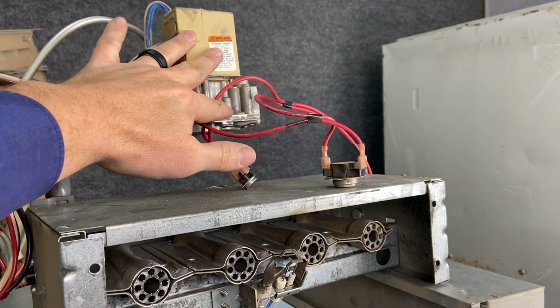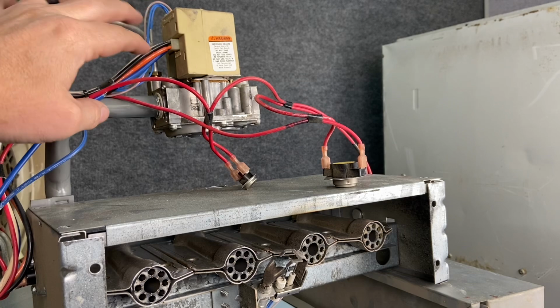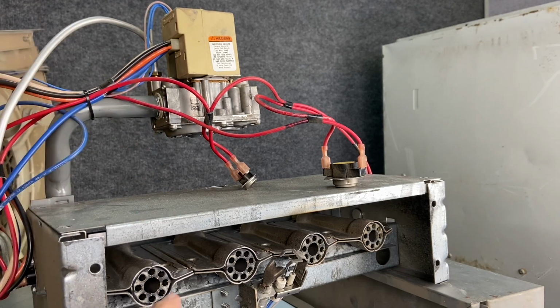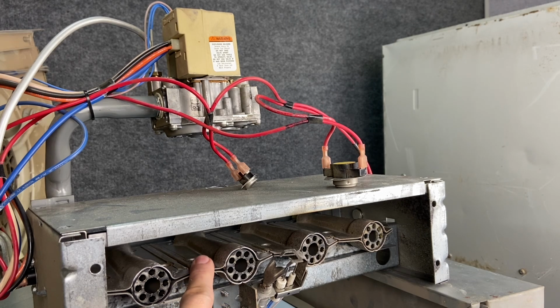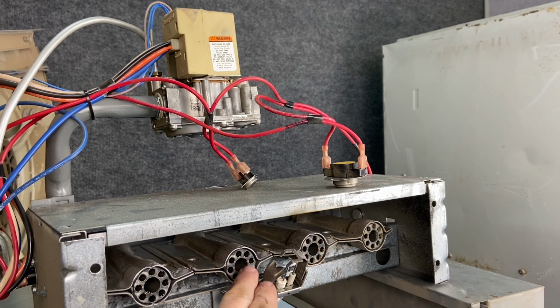So this is our smart valve, our combination gas valve, and we have our manifold here. On the back side you can't see it, but you have your spuds and your burners. These are the burners, in-shot burners, also called jets. Now if you can see right here, there's all of this corrosion on here. So these are 2 things that worry me. One is thinking it hasn't been serviced, but the other thing I'm thinking is, is there an issue with our gas pressure? Was it never set up right? So I think that's probably most likely the issue, that this gas wasn't burning correctly, wasn't mixing correctly, and we end up with all this soot on here.